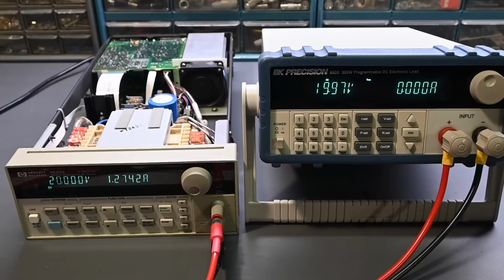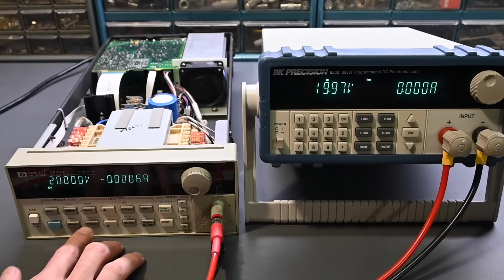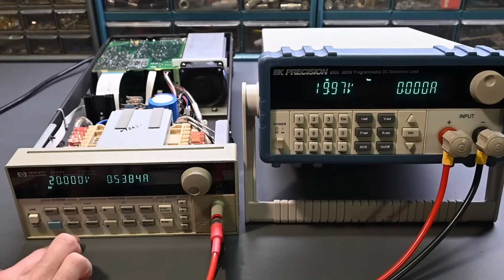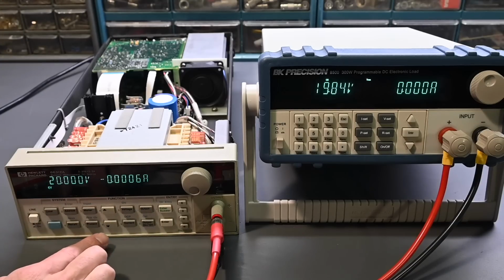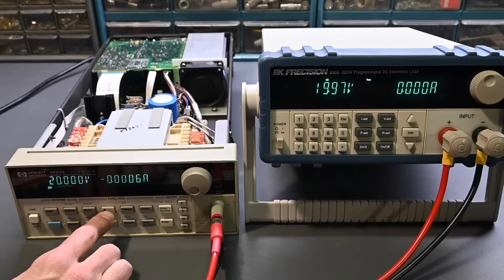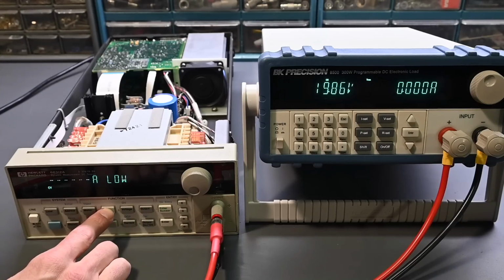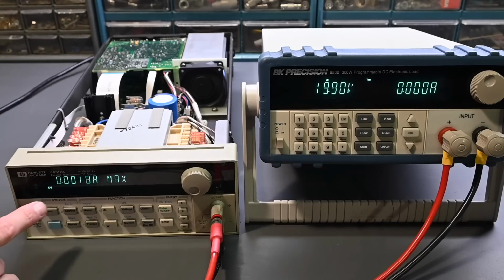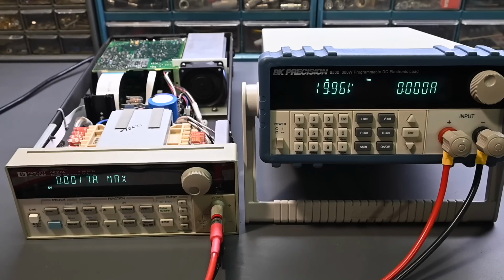However, if we go over here, the meter mode is just what it's in right now, so you don't have to press that, but that's just the standard mode. These up and down arrows will scroll through some extra functions and measurement readings. So if I go here to the maximum right there, so amps maximum, look at that, there it is. It happens quickly, but there's the 1.5, and that's what it displays most of the time. Sometimes it says 1.4, but most of the time it's right at 1.5. And that's exactly what the pulse is. So pretty cool. It can capture very, very fast transients and display them.